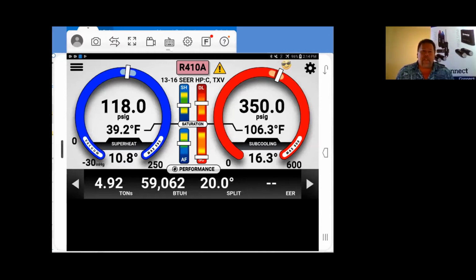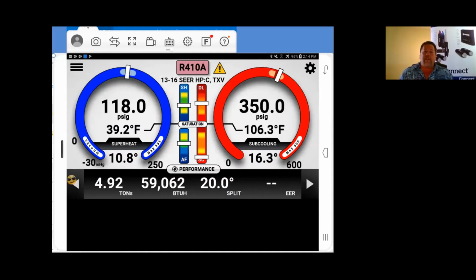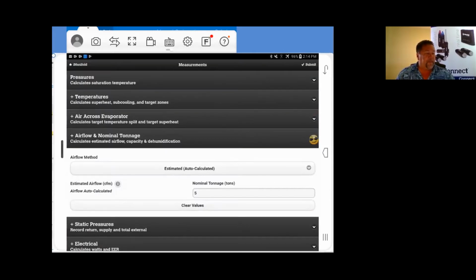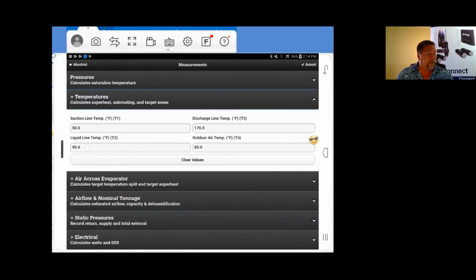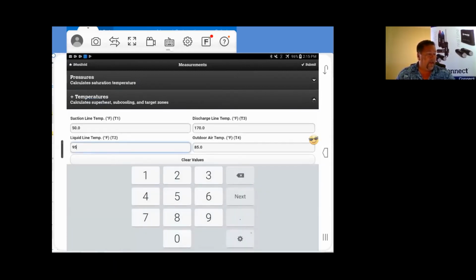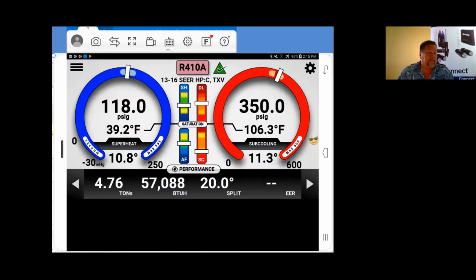So using the system with all this information that it's calculating for you, it's so much easier to get your job done. And you've got so much more complete measurements in there. You've got everything and it's ready to go. You're not having to calculate anything. It's doing all your calculations for you. Right here, we're taking a look at performance. 4.92 tons, 59,062 BTUs with a 20-degree split, but we've got high subcooling. And I know what's going on with that. That's a matter of having a little bit of a cold liquid line. If I just bump that up right there, we're back in business and we're good.